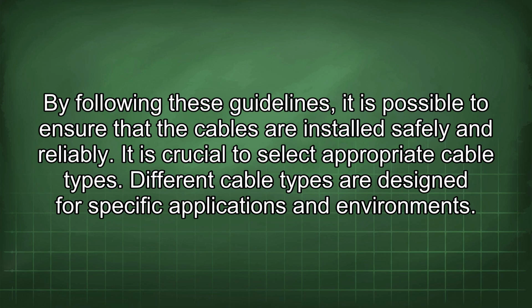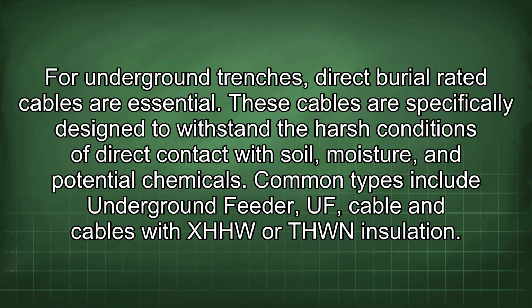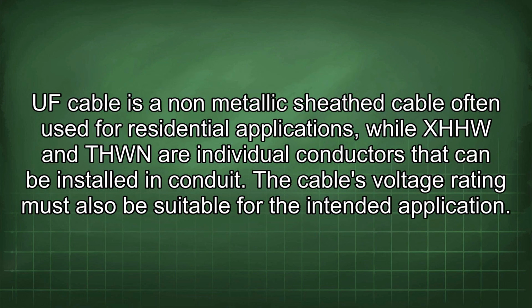It is crucial to select appropriate cable types. Different cable types are designed for specific applications and environments. For underground trenches, direct burial rated cables are essential. These cables are specifically designed to withstand the harsh conditions of direct contact with soil, moisture, and potential chemicals. Common types include underground feeder, UF cable, and cables with XHHW or THWN insulation. UF cable is a non-metallic sheath cable often used for residential applications, while XHHW and THWN are individual conductors that can be installed in conduit.